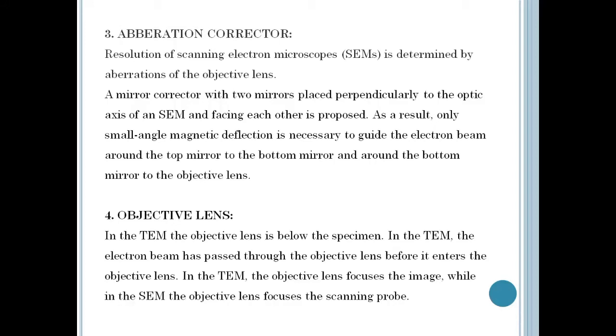The next part is the objective lens. In the SEM, the objective lens lies above the specimen, while in the TEM it is below the specimen. The SEM objective lens is the last lens in the series that creates the electron beam and scans the specimen, focusing the scanning beam to a very small spot. In the TEM, the electron beam passes through the specimen before entering the objective lens, where it focuses the image. In the SEM, the objective lens focuses the scanning probe. These lenses share the same name because they serve comparable functions in creating focus on the specimen, though they carry out focusing in different ways.